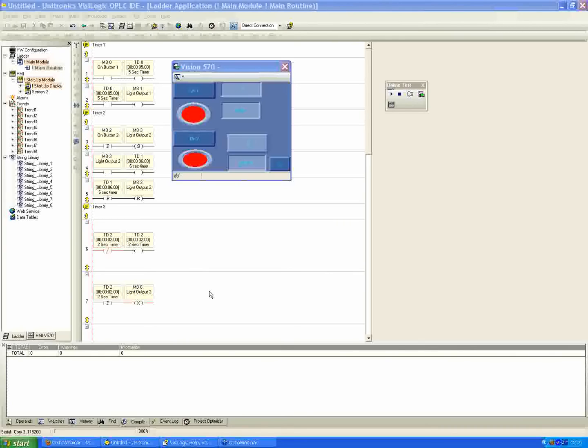Maybe I can answer by microphone. When we define a touch element — when we link a memory bit to a touch element — it starts to run as hardware, so it runs as an input. We cannot use the same element twice linked as a touch element to two operands, and we cannot use this memory bit as a coil because it operates like an input. The input is pressing the button.